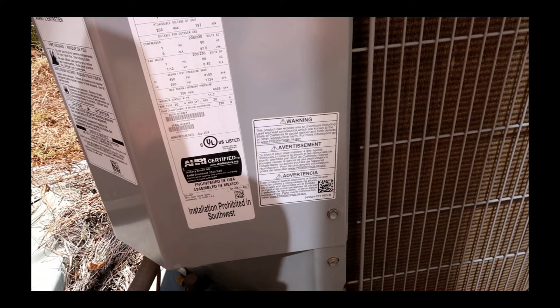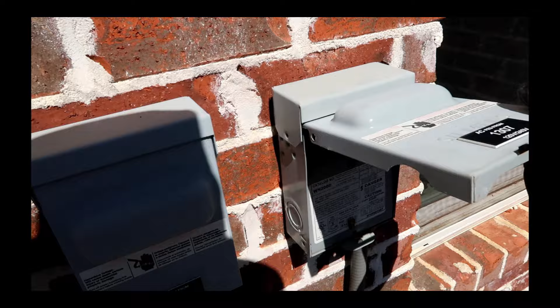Well, it's running, but the fan air is going down. I wonder if somebody put a capacitor on backwards, because I noticed the capacitor was new when I got here. I wonder if someone hooked up the capacitor wrong, because the fan's going the wrong way, as you can see. It's supposed to go clockwise, but it's running counterclockwise. Well, let me go get my stuff.